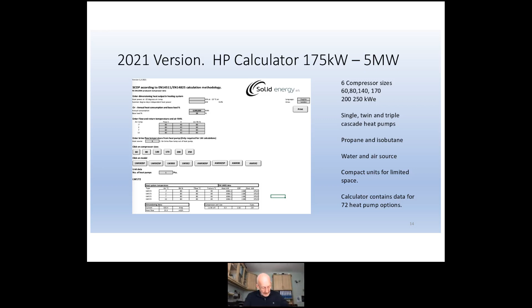Just to digress slightly, we've also got a thermal store calculator, which is useful, especially now when we need to potentially pick up cheap overnight electrical tariffs. Thermal storage is really essential for that, and also to reduce costs. We're now looking at thermal storage as part of demand side control, where the grid can instruct large heat pumps to come on and off, and we can add potentially 20% savings to the running costs of heat pumps if we bring in demand side control.